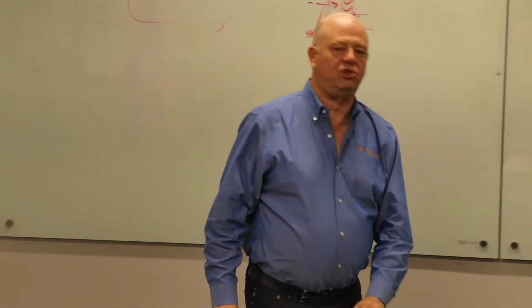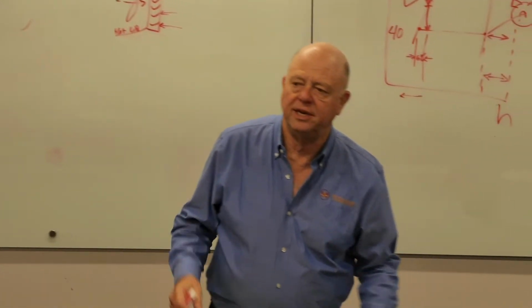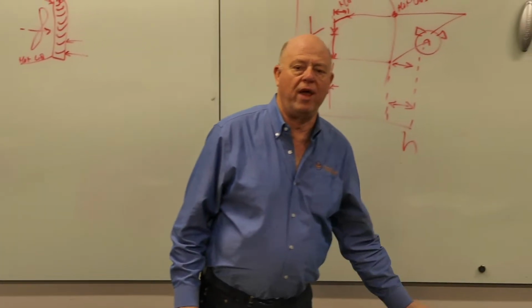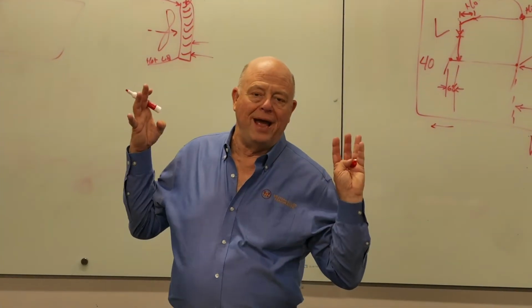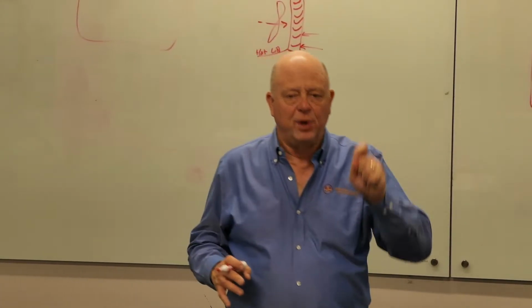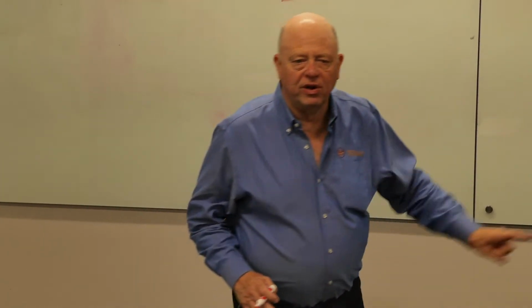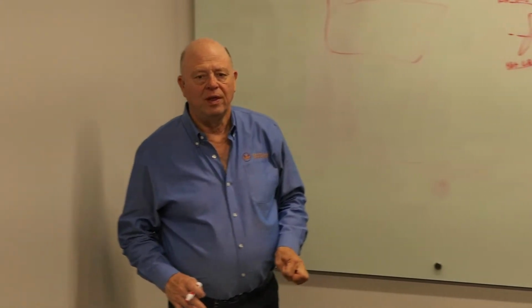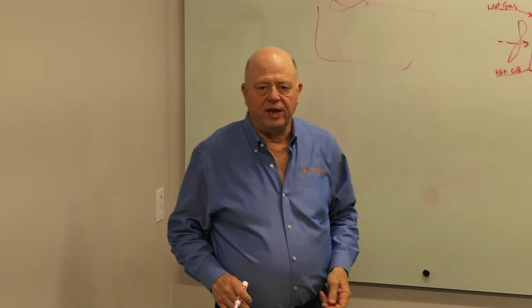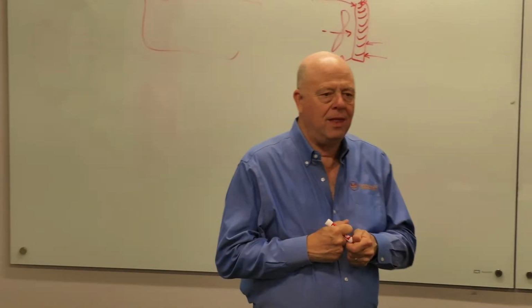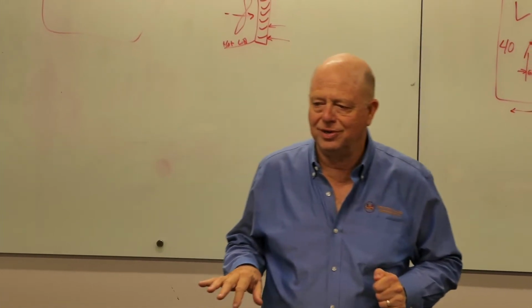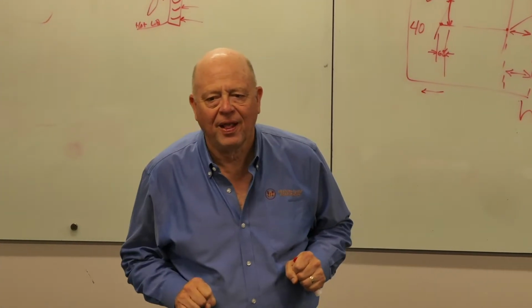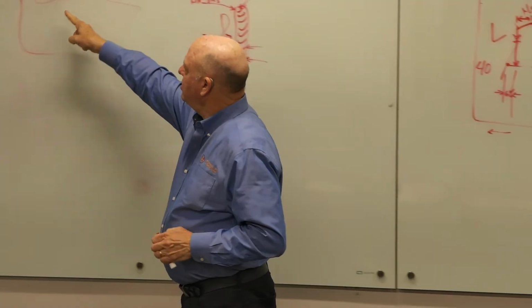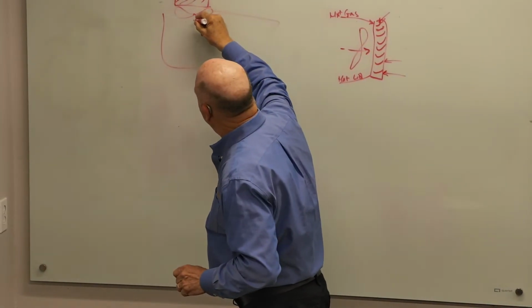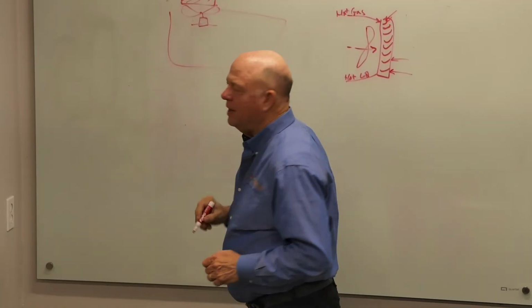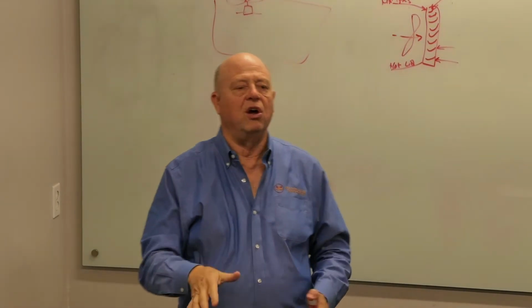Carrier had just, in 1978, because this was 1980, a year or two before that come out with what they called Motor Master, and it was the very first variable speed application for a condenser fan motor. So, as with all things, the first round didn't go exactly as Carrier expected. That condenser fan motor, sitting there with its little bracket holding it in place, is the cheapest piece of junk on the whole unit.